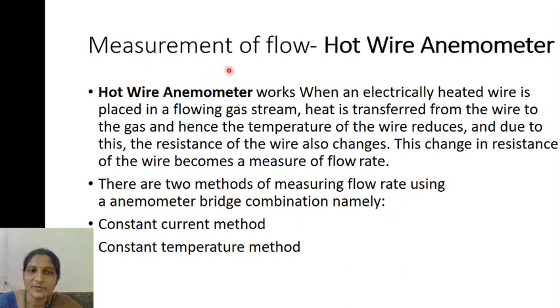Next one is the measurement of flow. Here, flow means fluid flow, and the fluid can be either gas or liquid. This flow can be measured by using a hot wire anemometer. The hot wire anemometer works when an electrically heated wire is placed in a flowing gas stream, and heat is transferred from the wire to the gas, and hence the temperature of the wire reduces and its resistance changes. This change in resistance of the wire becomes the measure of flow rate. Usually, the hot wire anemometer can be operated in two ways: the first is the constant current method, and the second is the constant temperature method.